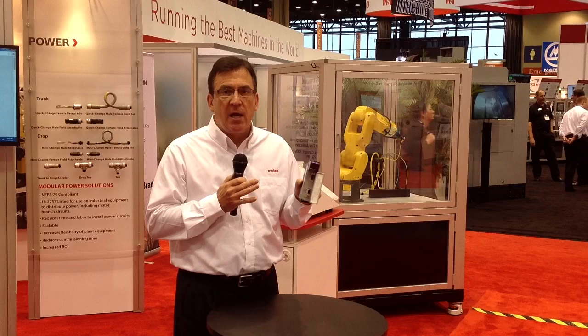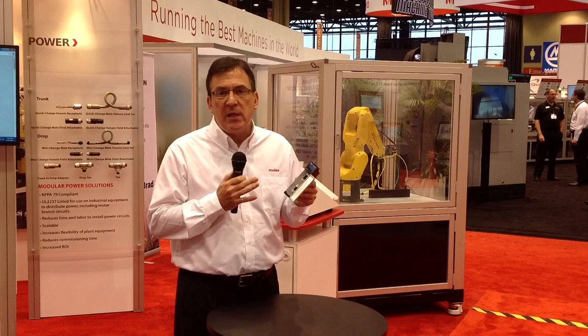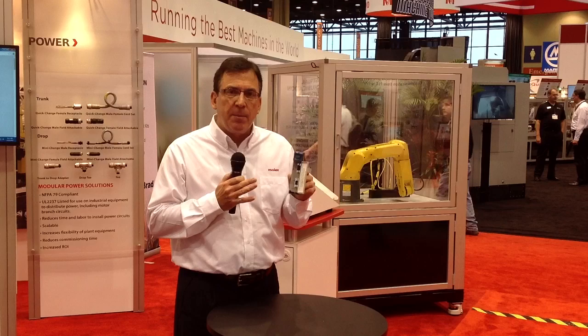It allows up to 244 words of data exchange between this module and the PROFIBUS master device. That PROFIBUS master can be another PLC, a DCS system, or even a PC-based control system. Up to 244 words can be exchanged between this card and the master.